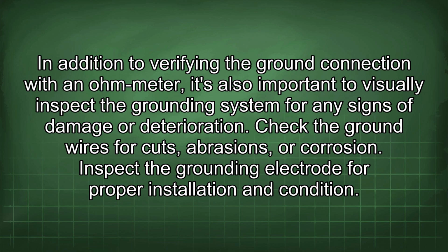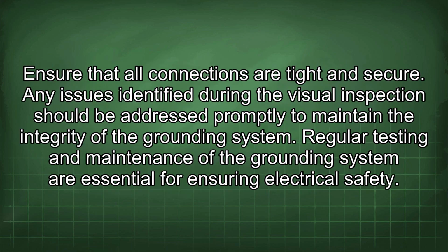Check the ground wires for cuts, abrasions, or corrosion. Inspect the grounding electrode for proper installation and condition. Ensure that all connections are tight and secure. Any issues identified during the visual inspection should be addressed promptly to maintain the integrity of the grounding system.